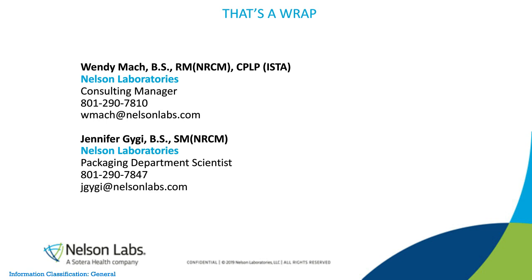Another question here asks, what are the biocomp requirements for packaging? That's a great question. The ASTM F2475 is currently under ballot. There is a table in that ASTM that identifies exactly what the requirements are. At a minimum, you're going to want to look at doing an MEM or a cytotox study.